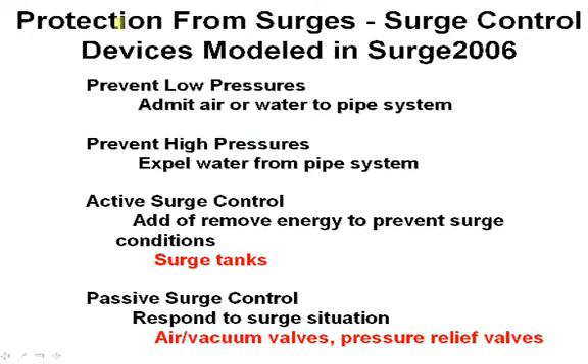How do you protect the system? There are several devices that we can use, and Surge2006 will deal with most of these devices. The devices are designed to prevent low pressure by putting air or water into the system, or prevent high pressure by expelling air or water from the pipe system. Active surge control will actually prevent the surge condition, and you need a surge tank or a similar device to provide energy to the system. Passive surge control may be less expensive but it doesn't prevent the surge — these are devices like air vacuum valves and pressure relief valves.